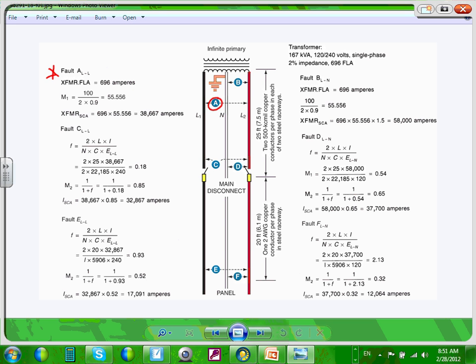So let's go right. We always start by the transformer, right at the terminal of the transformer. Right at the terminal of the transformer, guys, here's the information about the transformer that I have. I have a 167 kVA transformer, 240 volts, single phase, 2% impedance, and full load current of 696 amps. Full load current of 696 amps. Okay? Any question about what we have?